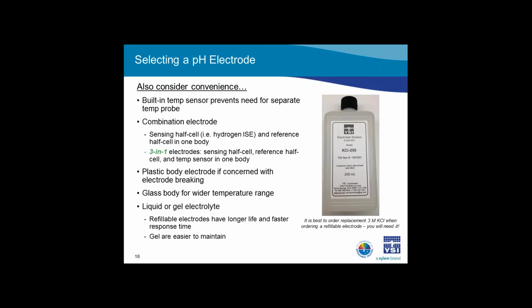It is also important to consider the likelihood of the electrode being banged around in the lab. If this risk is high, perhaps it is best to go with a plastic body electrode. Also, if you are concerned with the electrode being properly maintained, it might be best to get a gel-filled electrode, as they do not need to be refilled with electrolyte. However, if you would like the electrode to have a faster response time and a longer life, a refillable electrode is the way to go. If ordering a refillable electrode, don't forget to also order some replacement KCl solution. It will definitely come in handy.